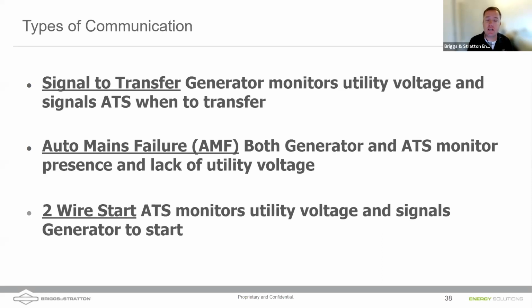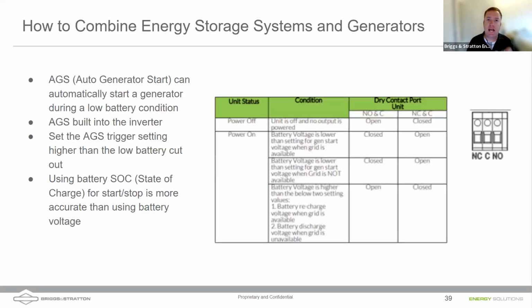What you can do is get into our GC1031 controller and disable that auto mains failure sensing, right? So tell it that even if it still sees voltage, listen for that 2-wire signal to start, and it will still start up. So these are the different ways to do that, and how we send the signal to the generator. In our case, it's a normally open circuit. So when these 2-wire signals are sent by an inverter, it will close the 2-wire signal. The generator will sense that and automatically start up.